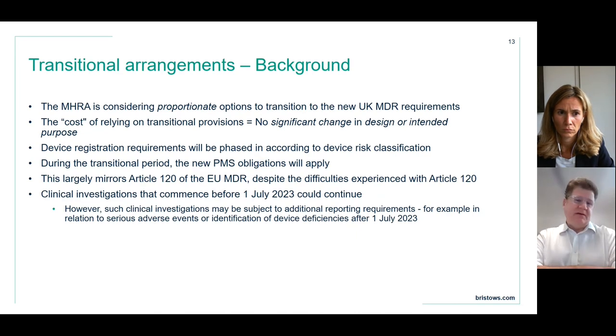As for transitional arrangements, the MHRA is adopting a very flexible, accommodating approach, a more proportionate set of options. Much like the position in the EU MDR, the cost of relying on the transitional provisions is that there can be no significant change in design or intended purpose during the transitional period. The device registrations will be phased in according to device risk classification, and during the transitional period, the new PMS obligations will apply.